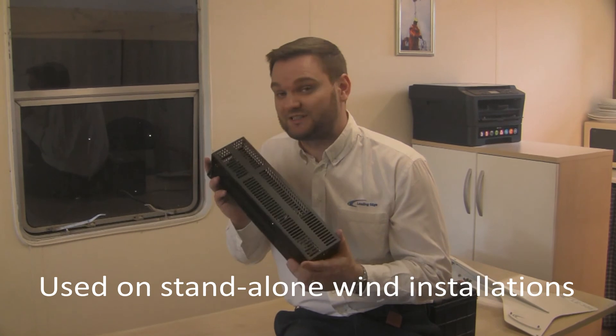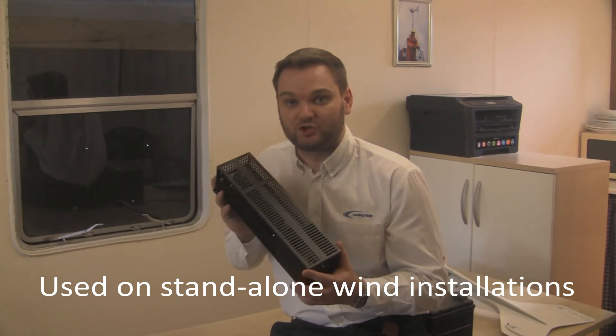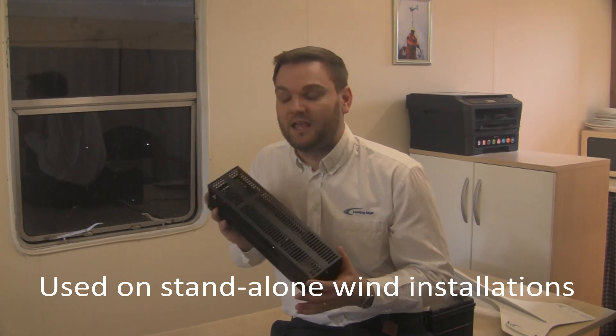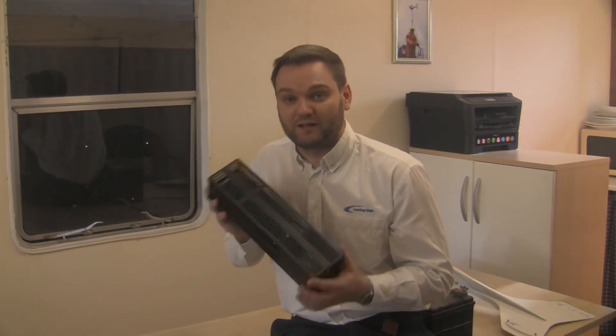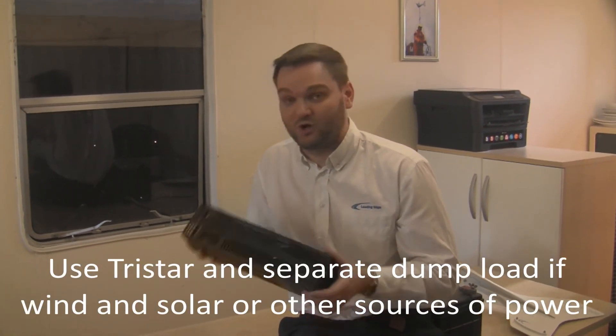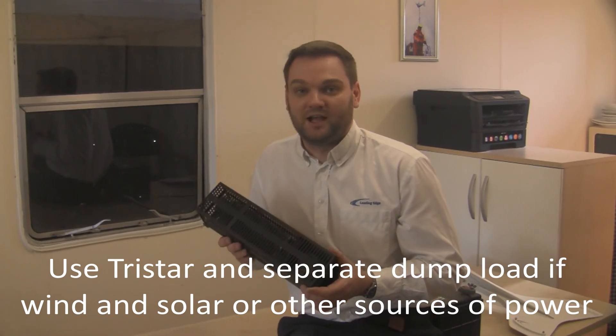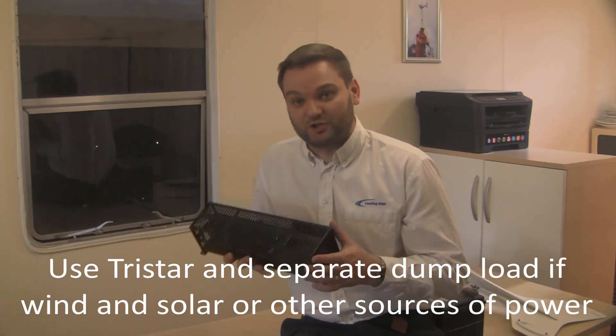Typically this will be used on standalone installations where you simply have a wind turbine charging a battery bank. If you're using more advanced charging techniques, maybe solar as well and other charging sources like diesel or hydro, I recommend that you use a TriStar controller and a separate dump load. The TriStar is slightly more expensive but offers much more flexibility in configuring the system.